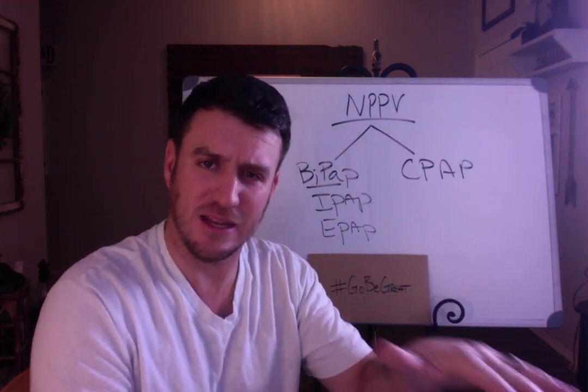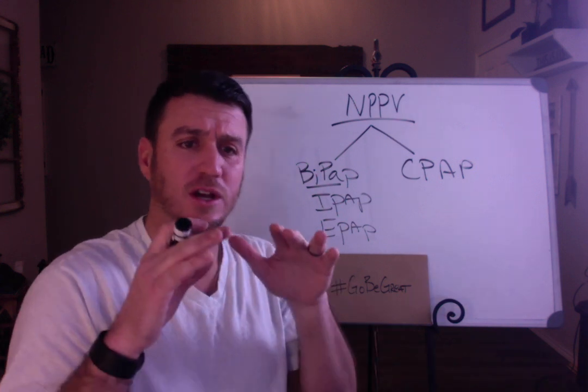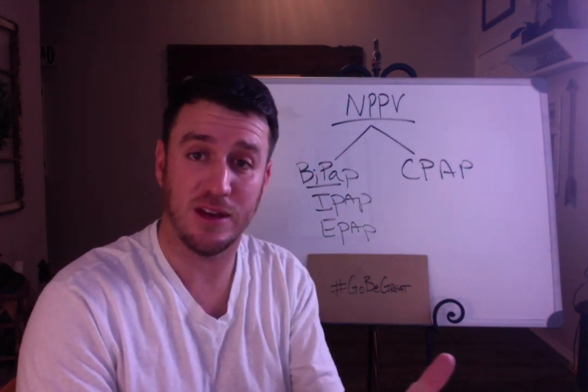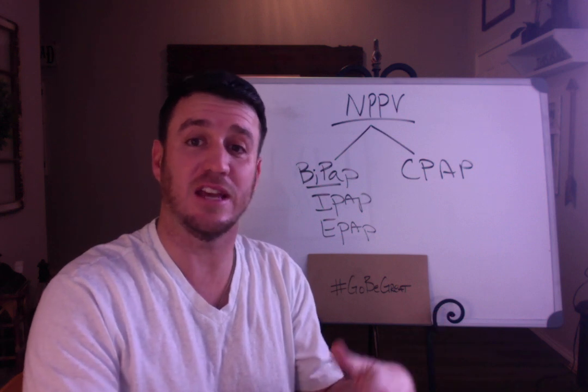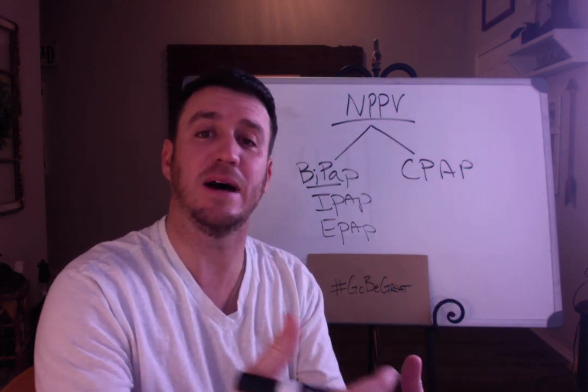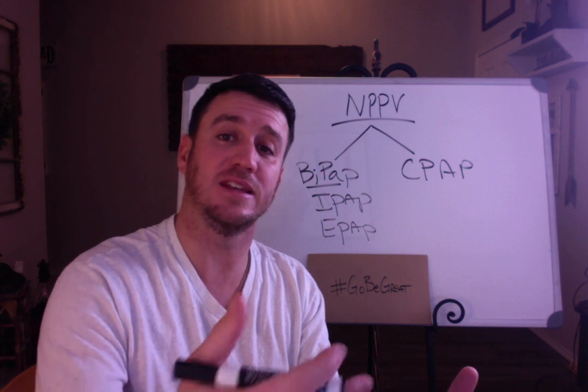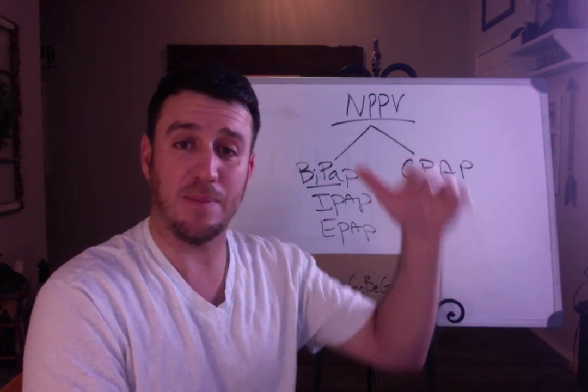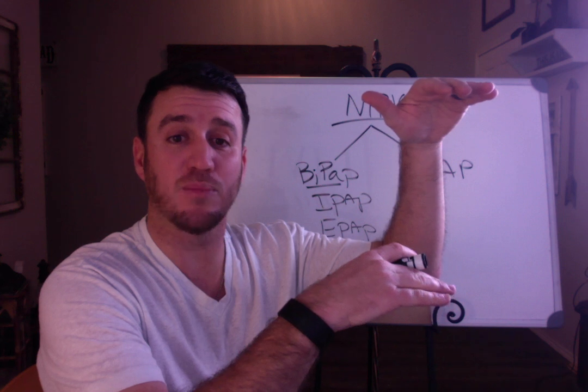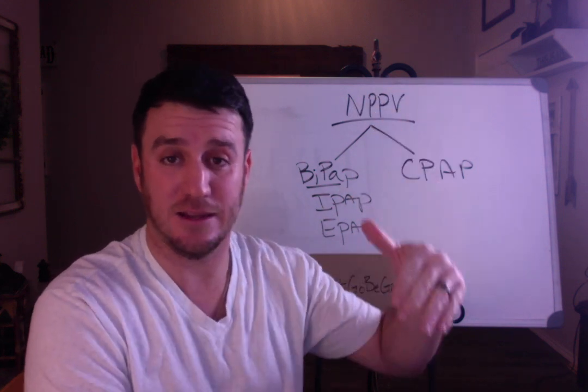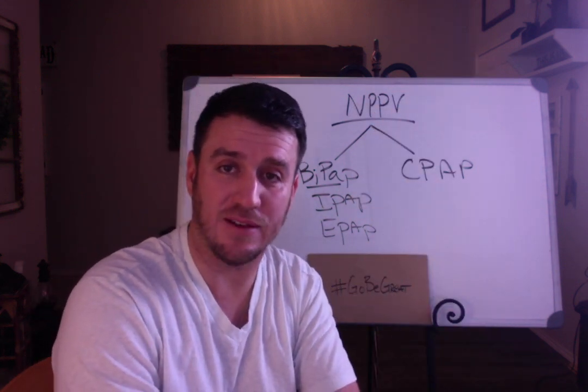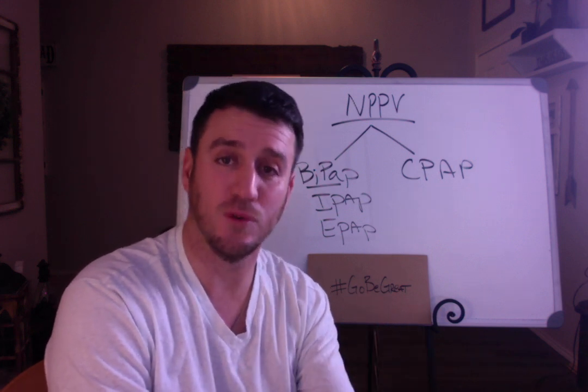Your pressure support is going to be the difference between your IPAP and your EPAP. So if you have an EPAP setting of 5 and an IPAP setting of 15, your pressure support is the difference — IPAP of 15 minus EPAP of 5 equals a pressure support of 10. And that's what's going to drive your CO2 removal.